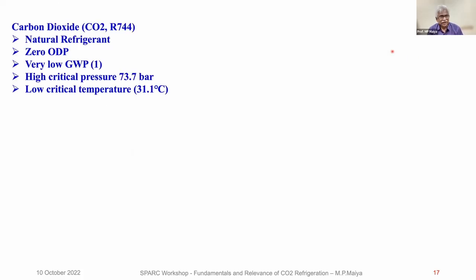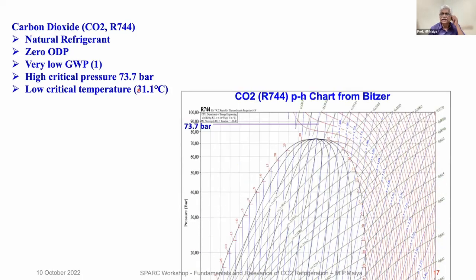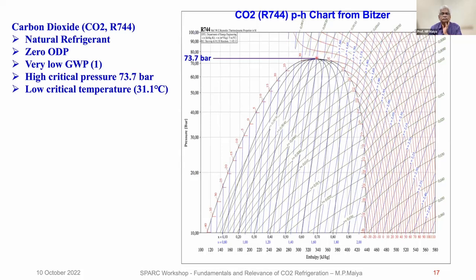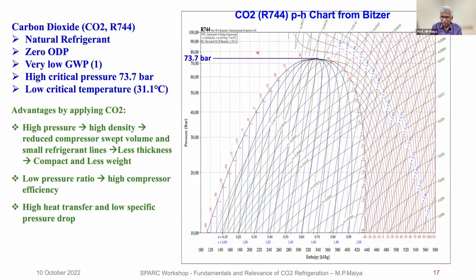Now, carbon dioxide is a natural refrigerant, zero ODP, very low GWP, just 1, compared to HFC-134a at 1000, 2000, 3000. So it is negligible. It has high critical pressure and low critical temperature. You can see this is the CO2 p-h chart. The critical pressure is 73.7 bar, high pressure. We have to convert high pressure into an advantage. When high pressure is inevitable, you try to use it to advantage.